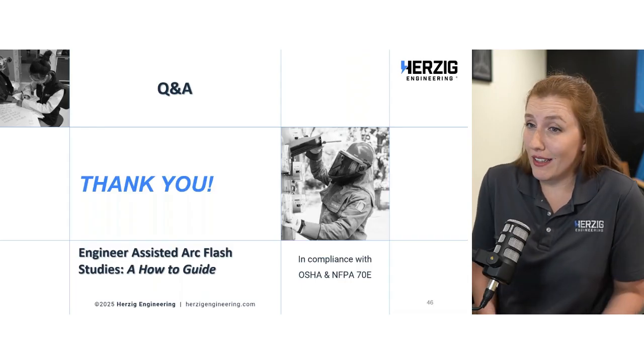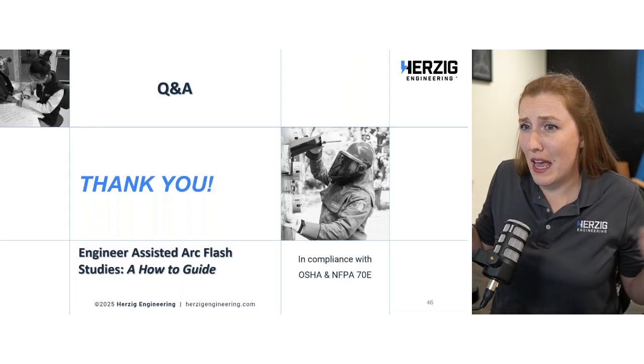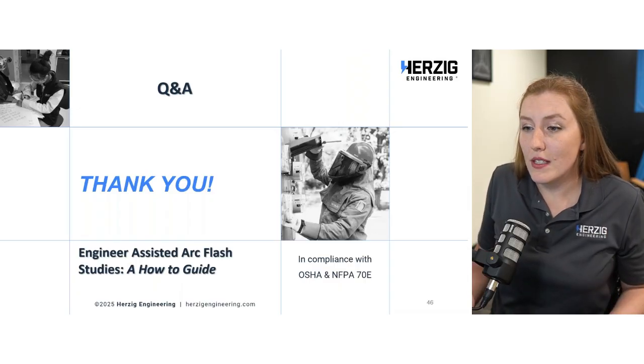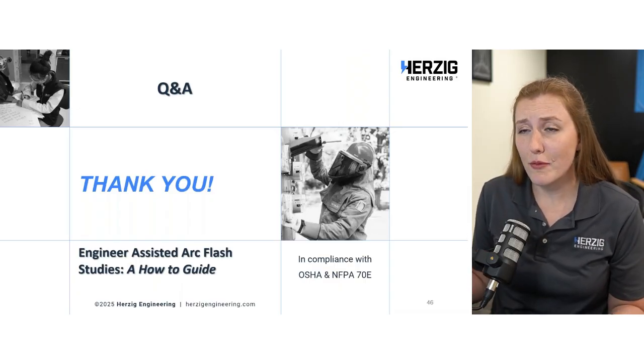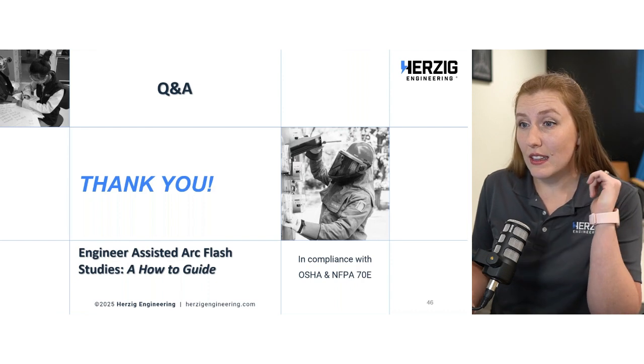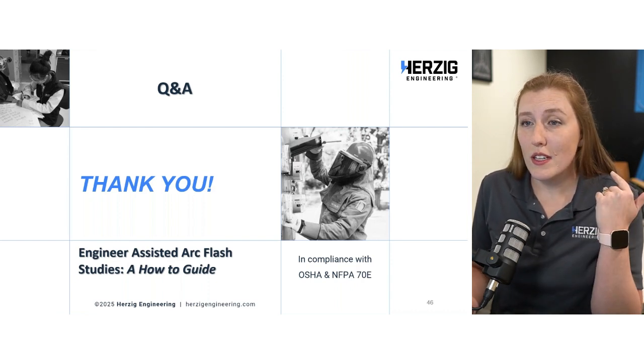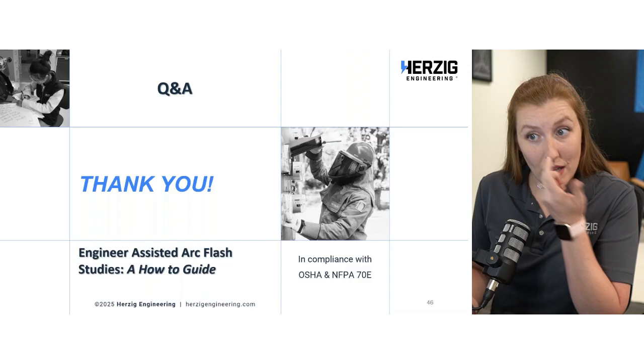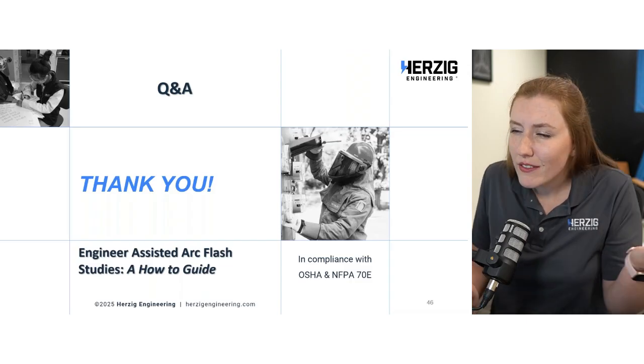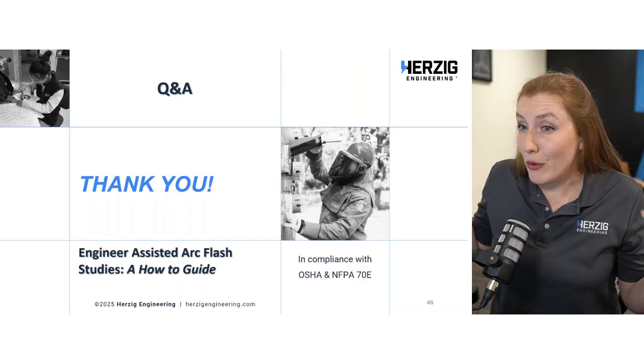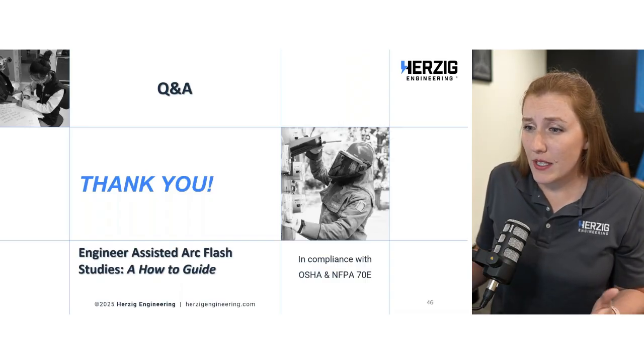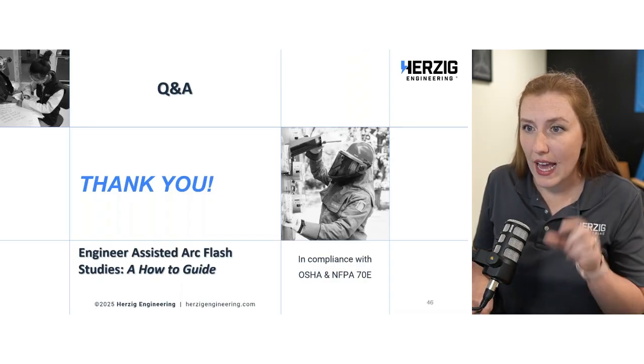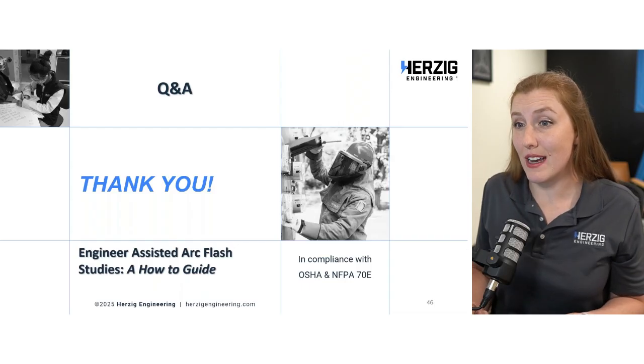If that's legit, if there's just no need for maintenance ever, technically no, because the NFPA 70E says anything likely to require examination, adjustment, servicing, or maintenance, right, while energized. And you have to act like it's energized until you verify it's off. So if you're really never ever going to get into it while it's on, that element right there maybe does not need a label.